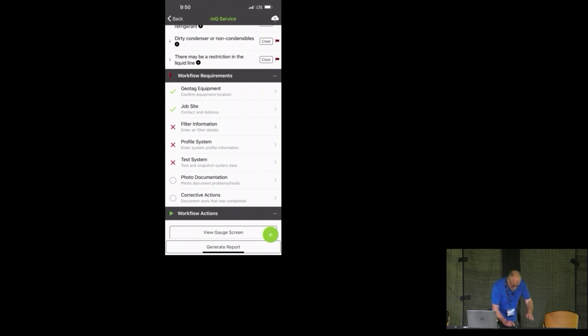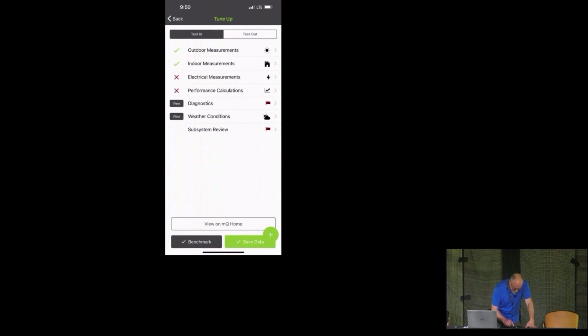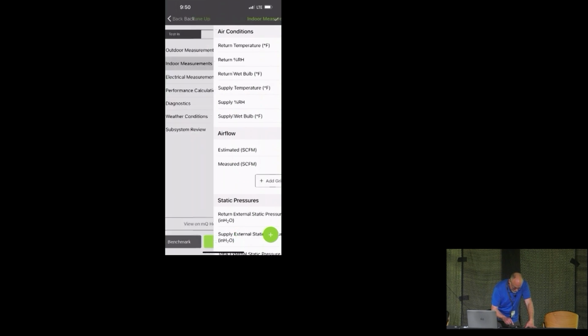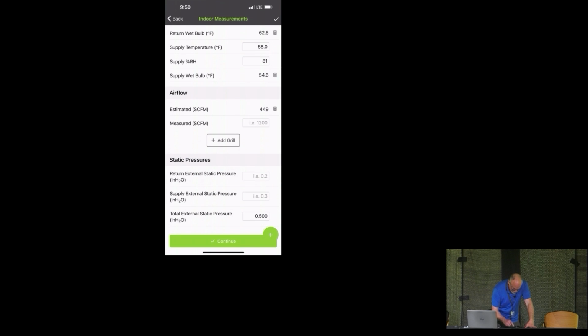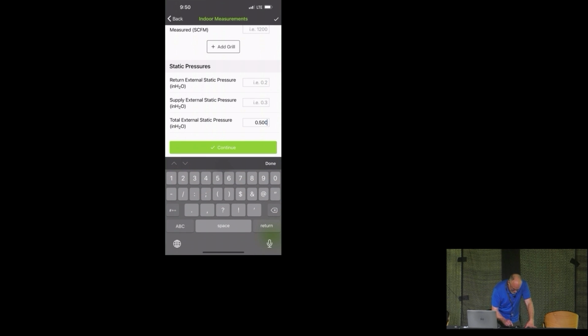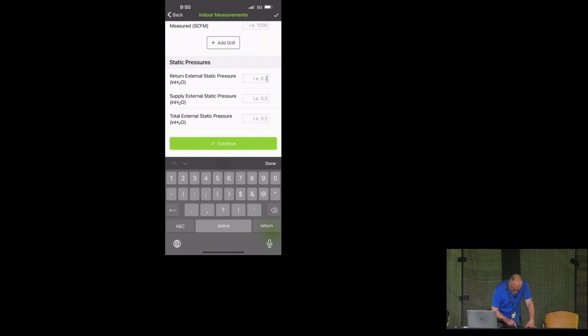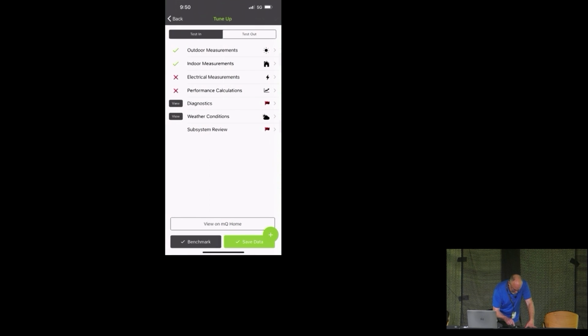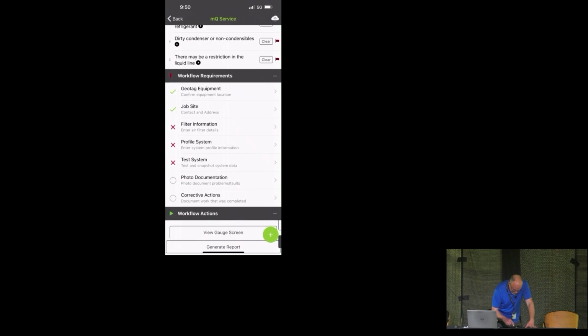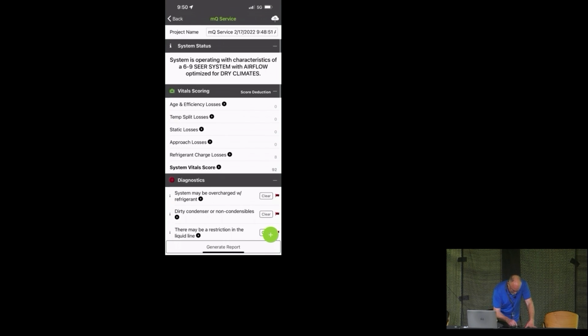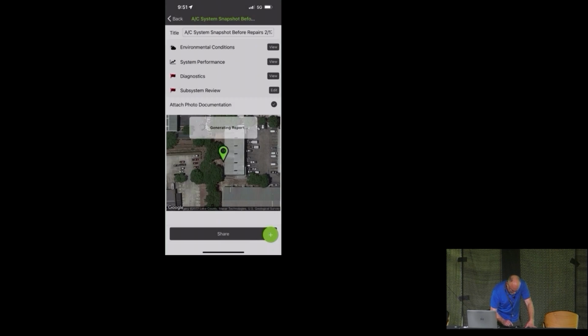But as we put in new measurements, let me just go in here, I'll test the system, and we'll just put some indoor measurements here, static here. So we'll clear out this 1/2 inch, and we'll just say it's 0.7 and 0.23, continue, and back, and we'll go back another one here, and then share, and this is where you're going to export your vitals report.